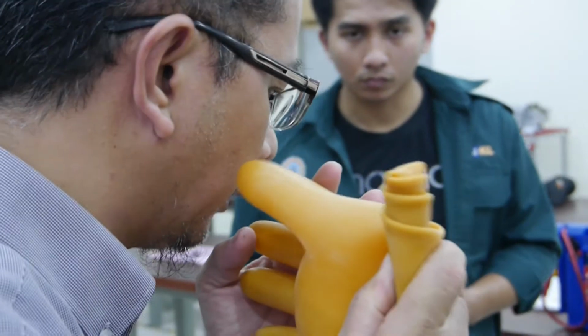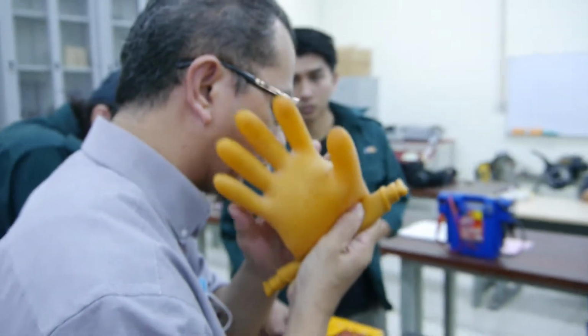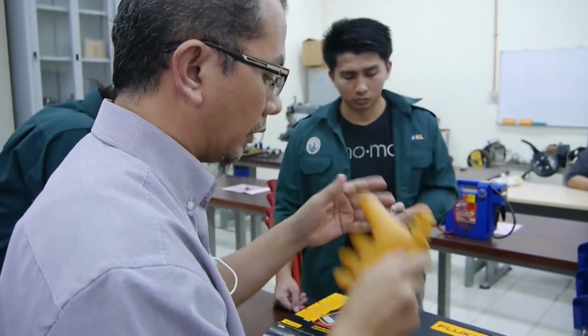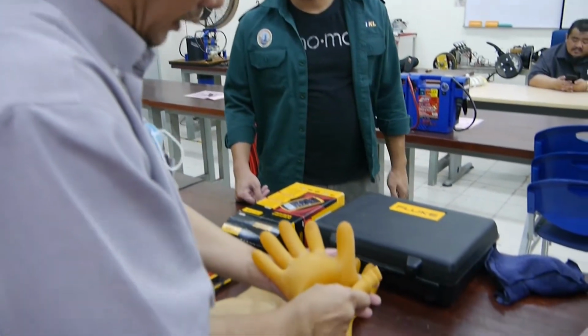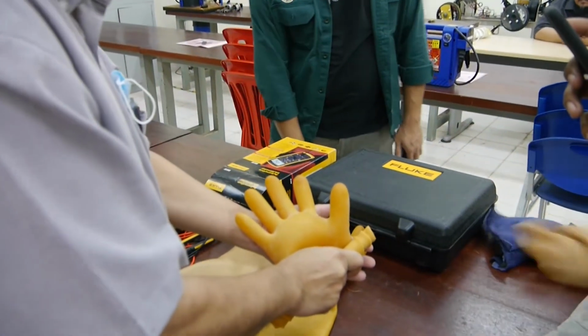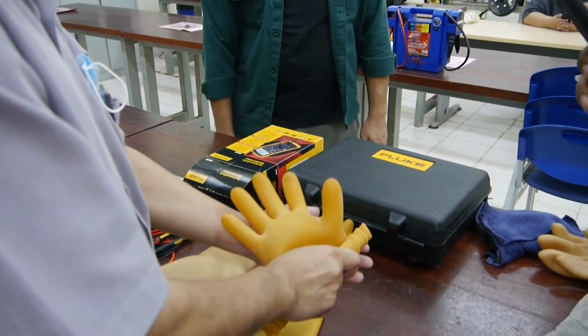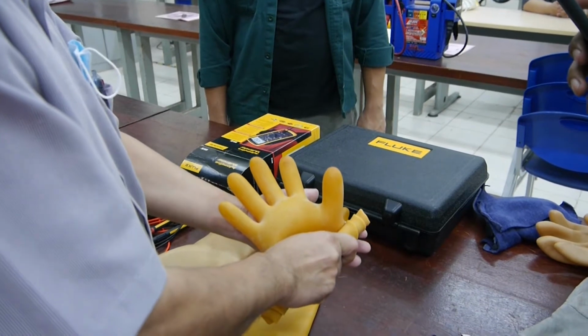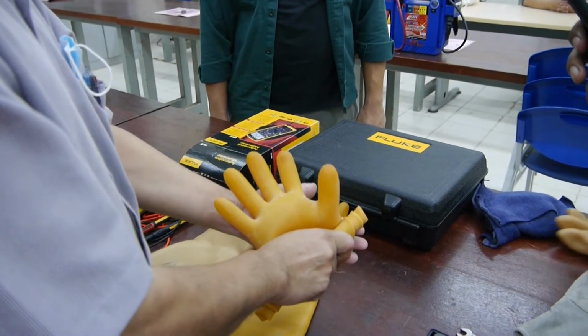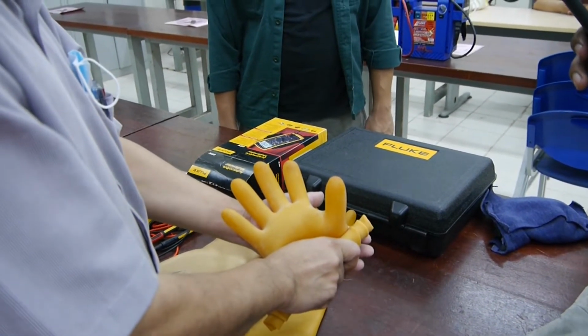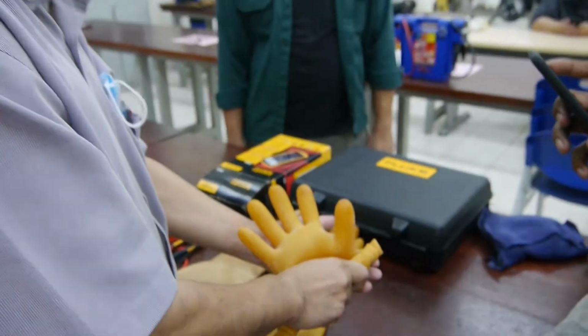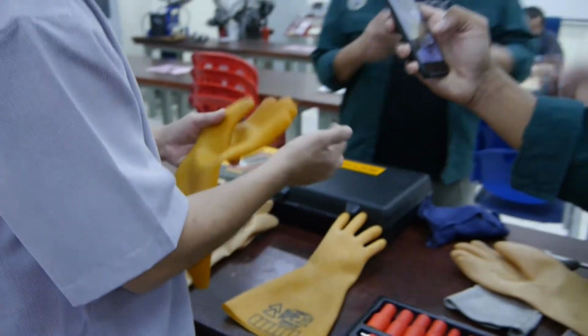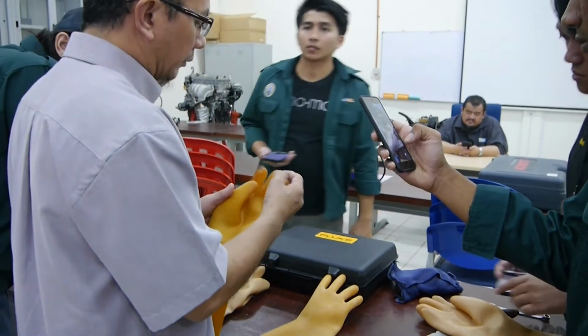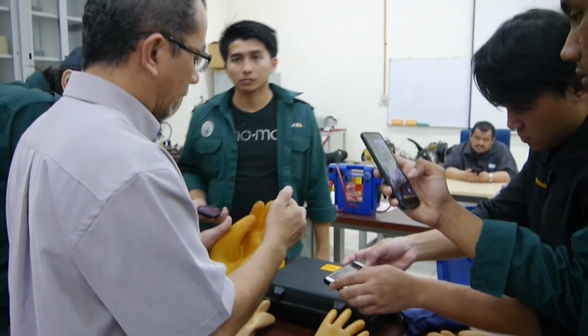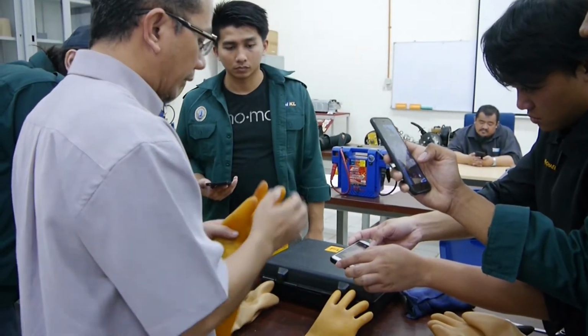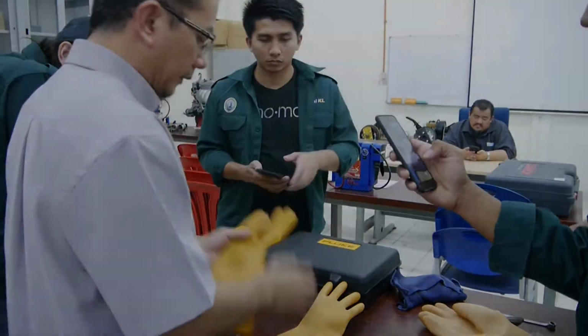To check for air leakage, we open the glove to let air through, then roll the glove as shown in the video. We then check if air blows through or the glove becomes flat. The purpose of this step is that current could jump through a leakage and cause a fatal accident.